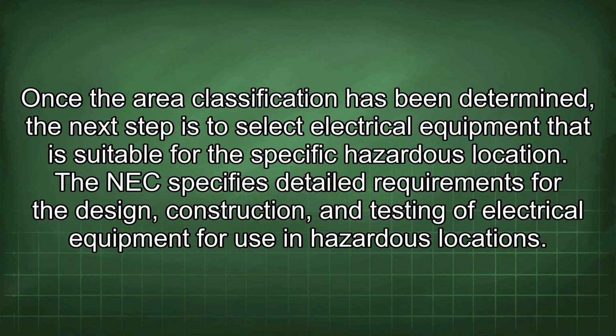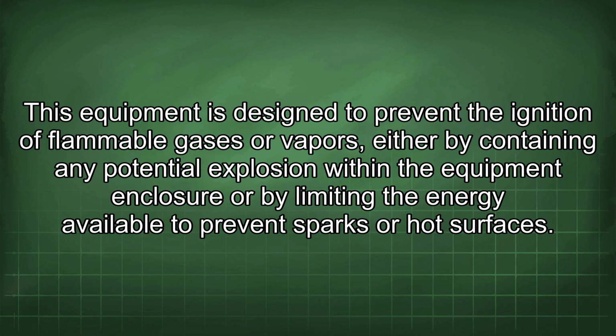Once the area classification has been determined, the next step is to select electrical equipment that is suitable for the specific hazardous location. The NEC specifies detailed requirements for the design, construction, and testing of electrical equipment for use in hazardous locations. This equipment is designed to prevent the ignition of flammable gases or vapors, either by containing any potential explosion within the equipment enclosure or by limiting the energy available to prevent sparks or hot surfaces.